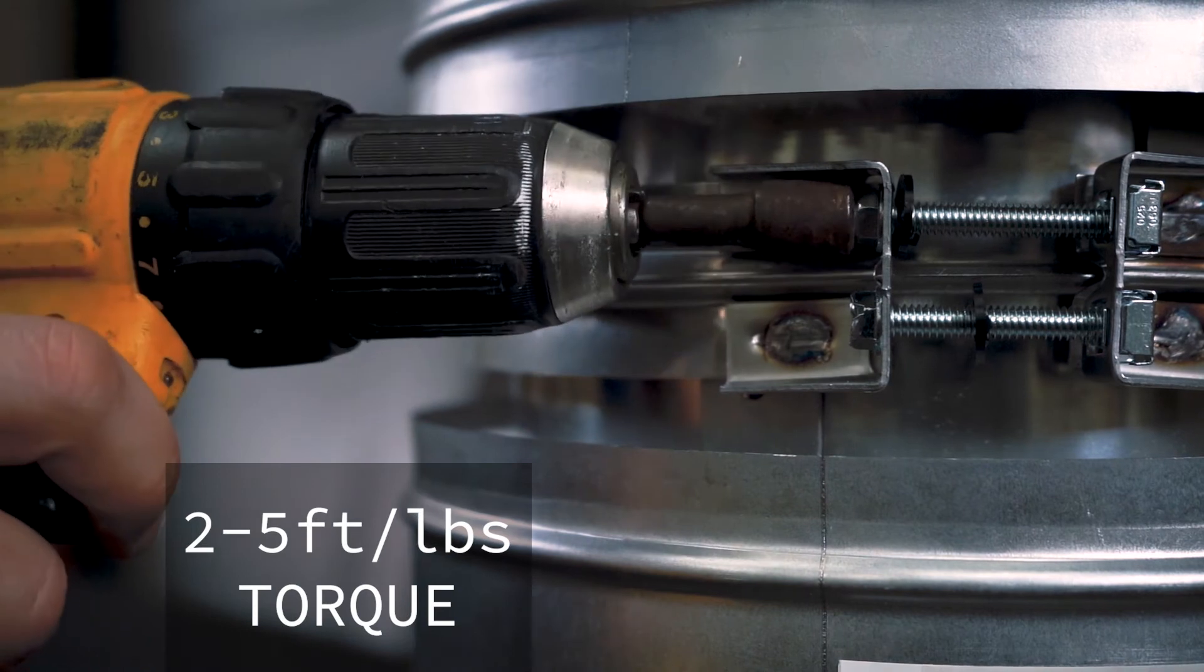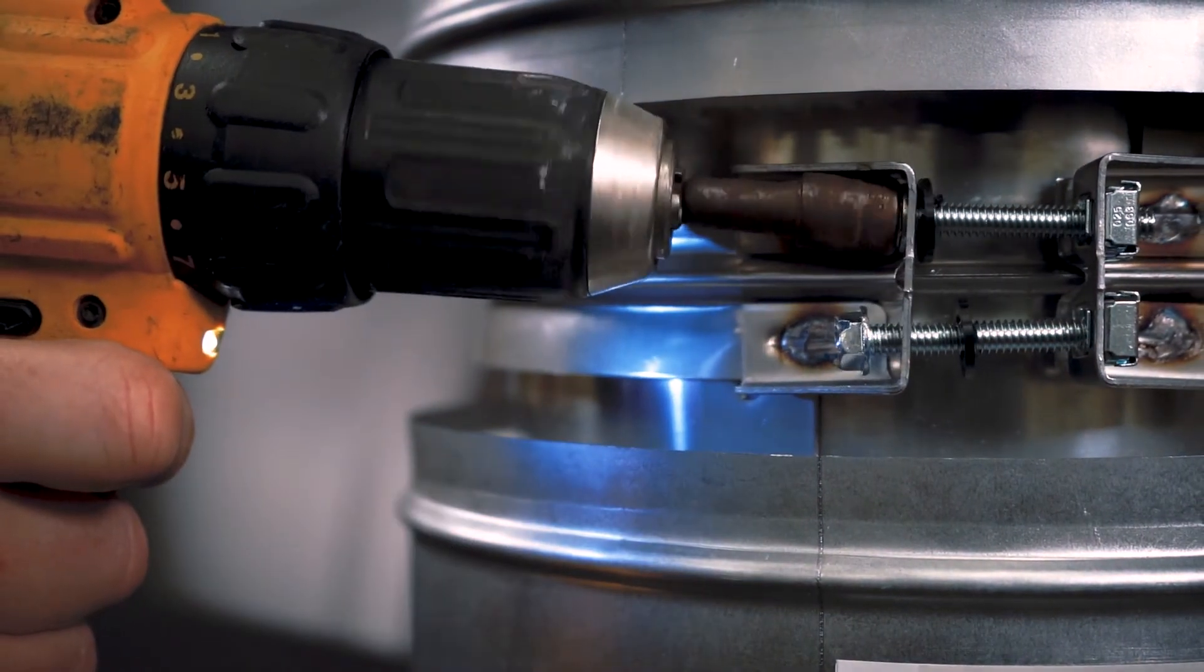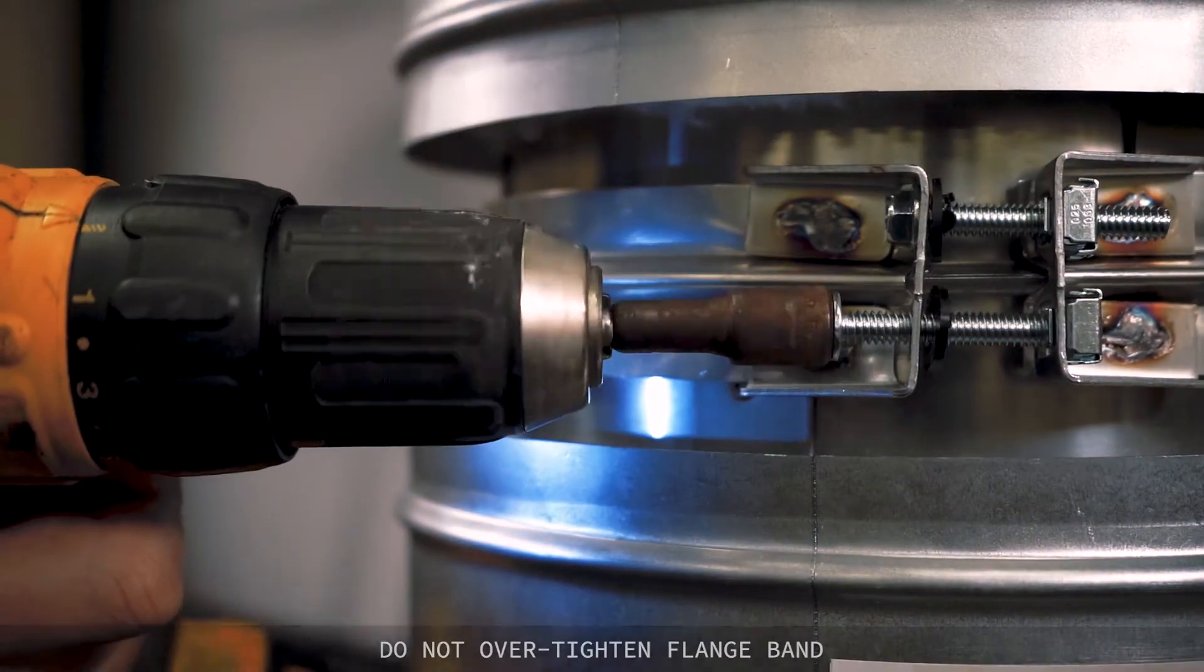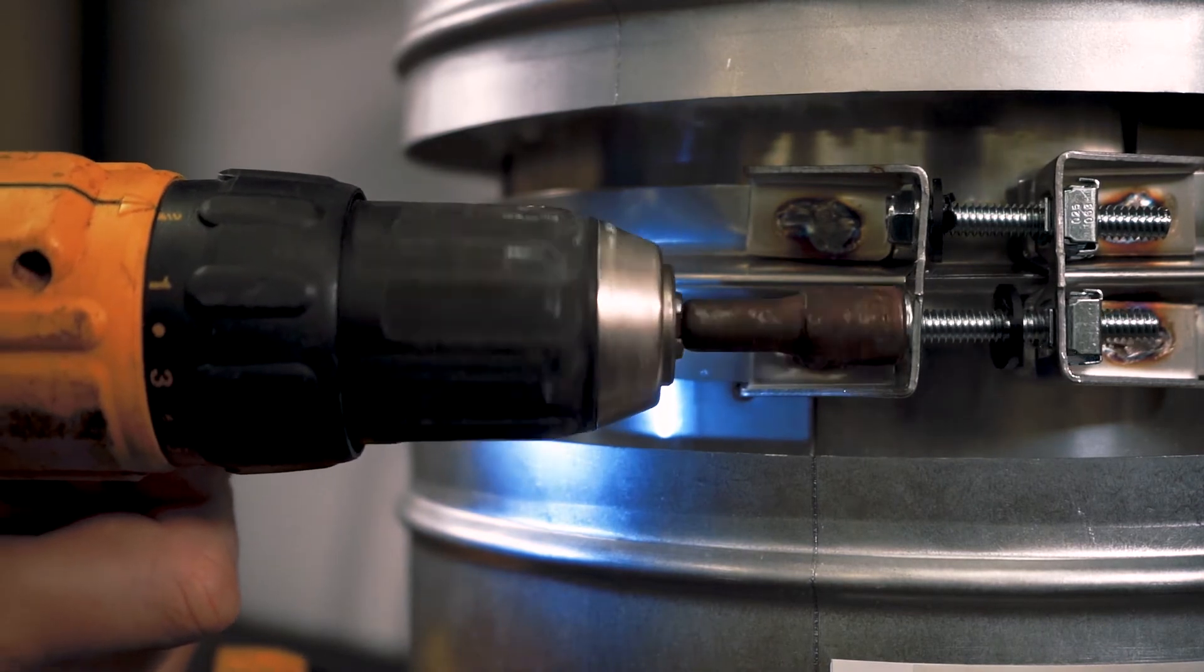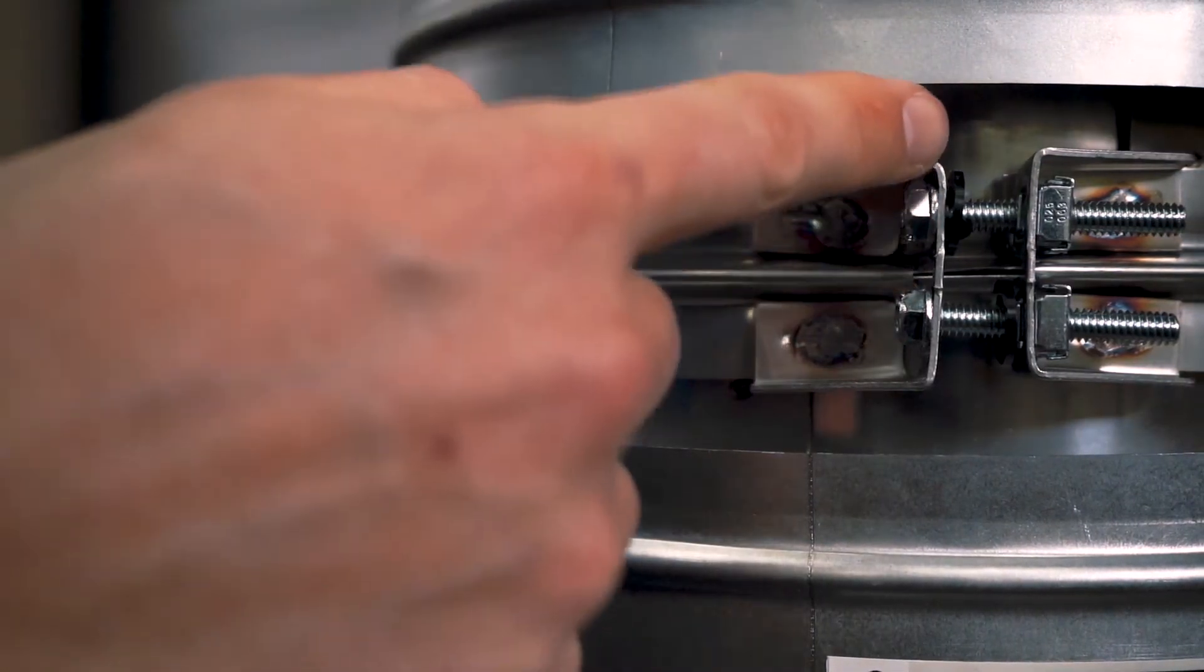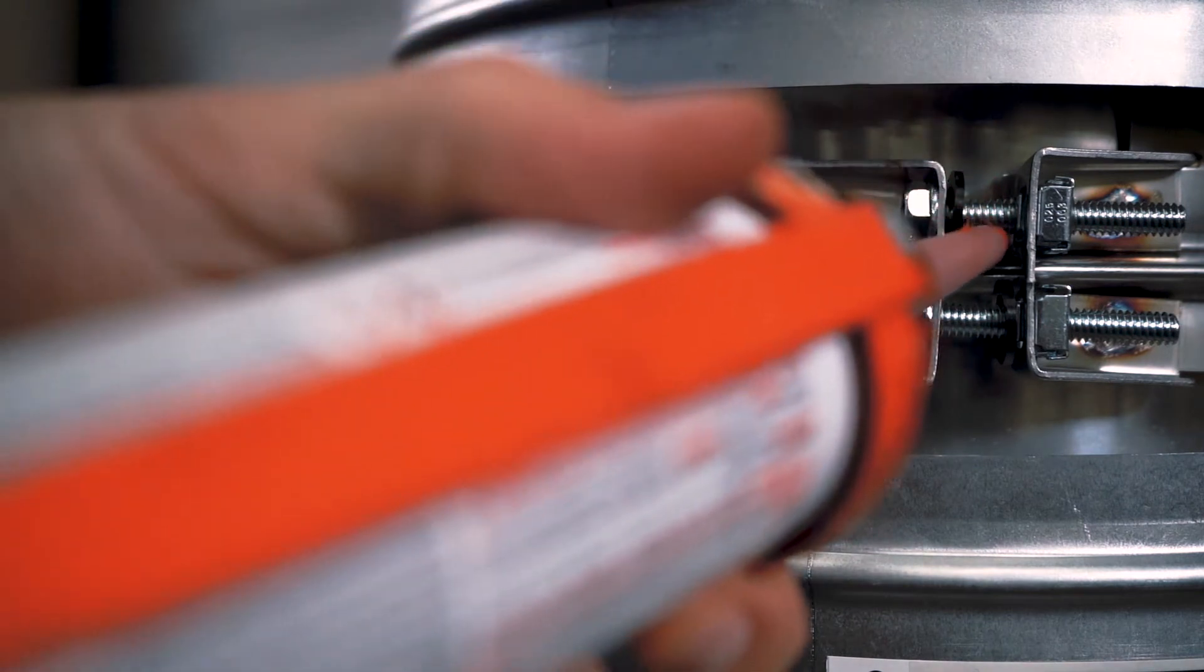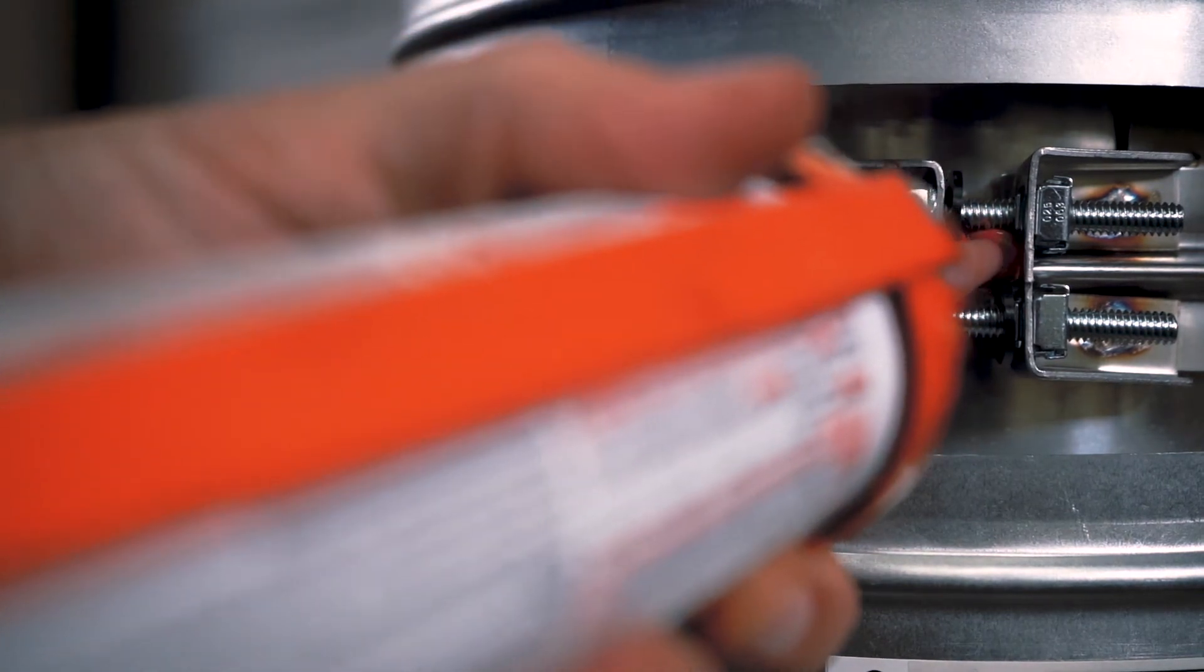Tighten the bolts between 2 and 5 foot pounds of torque. Do not over-tighten the flange band. When tightened appropriately, the two ends of the flange band brackets should not be touching. Fill the area between the bolts with sealant to ensure a leak-proof joint.